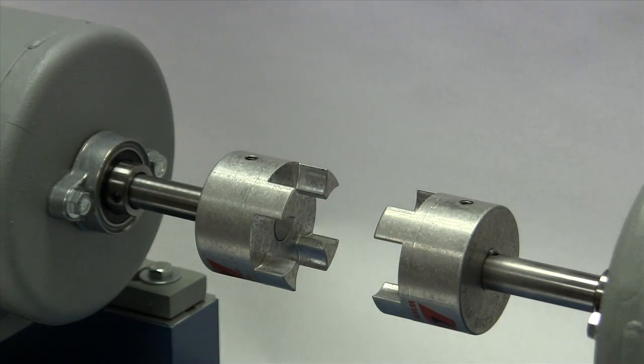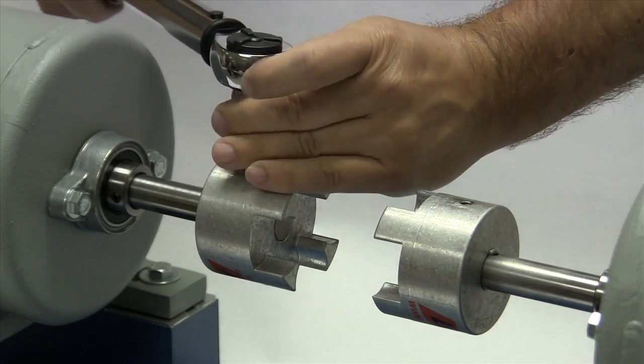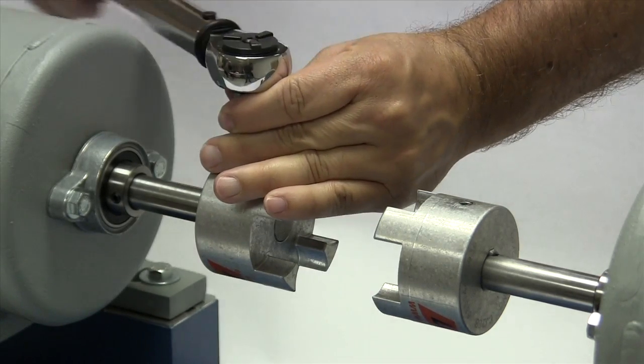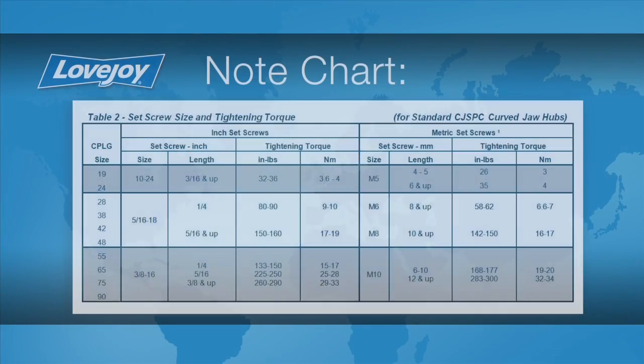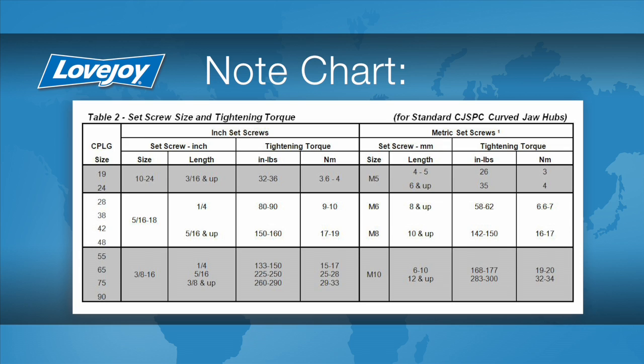The set screws should be tightened to the recommended torque settings using a calibrated torque wrench. The use of a torque wrench is important. If the set screws are not tightened properly, the hub could work loose and slide on the shaft. If the set screws are too tight, they could damage the key, the shaft, or the hub.